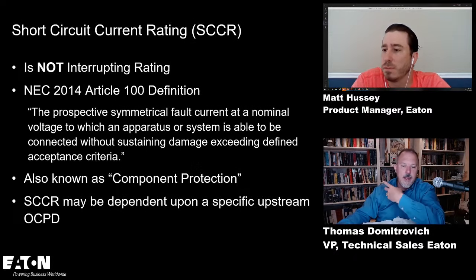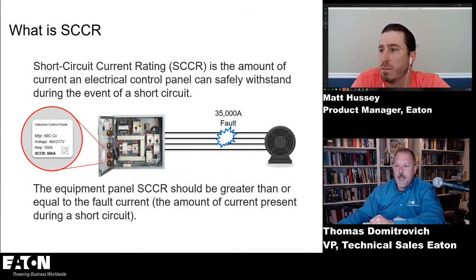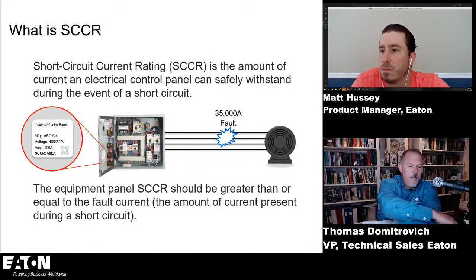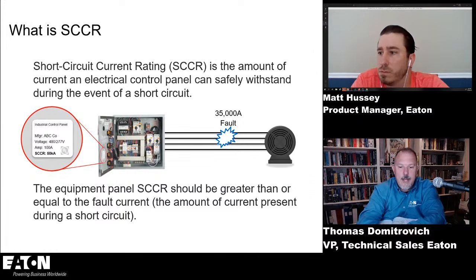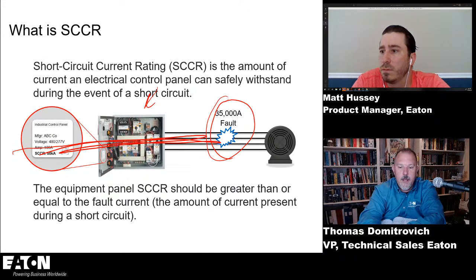And the best thing that I like, this diagram best because it really shows that the fault is actually not in the equipment. Like this would have to be the MCC. The fault is downstream, and then the current is passing through that equipment, and all of those components that are carrying the current have to hold it together under the pressure.